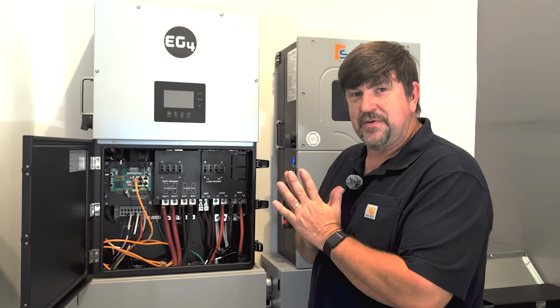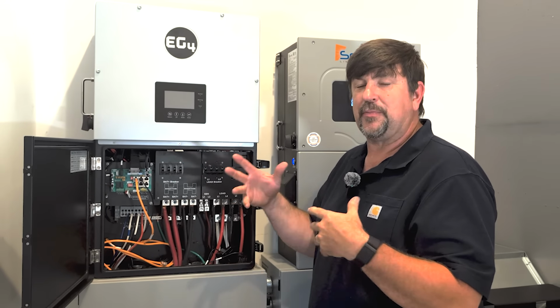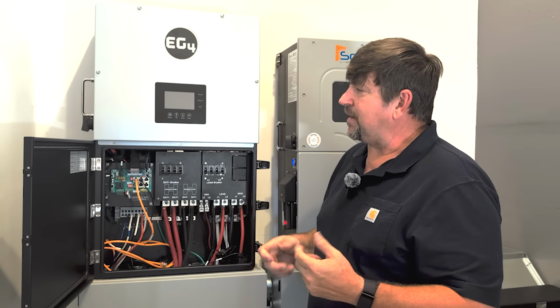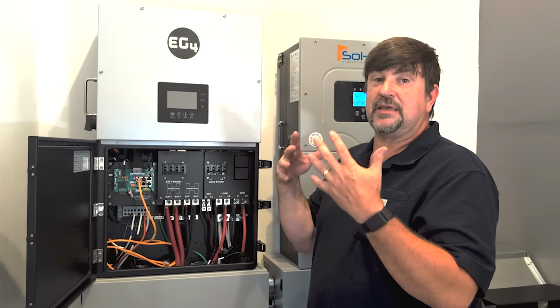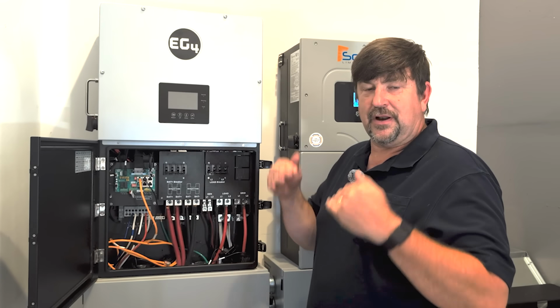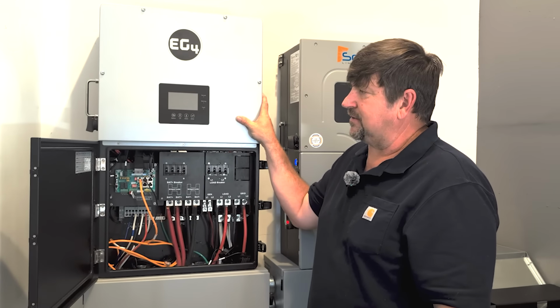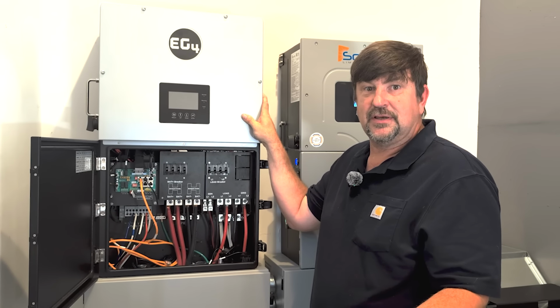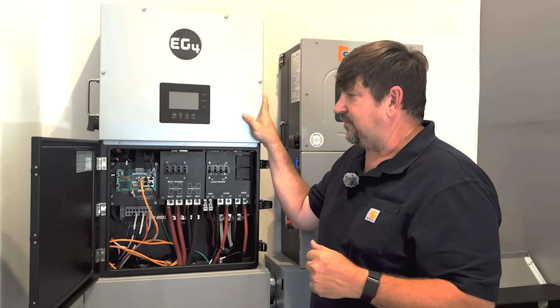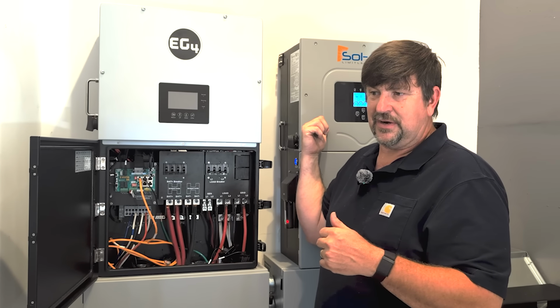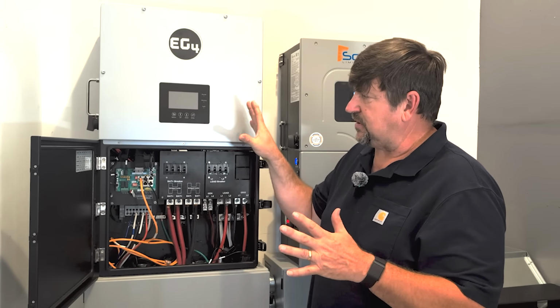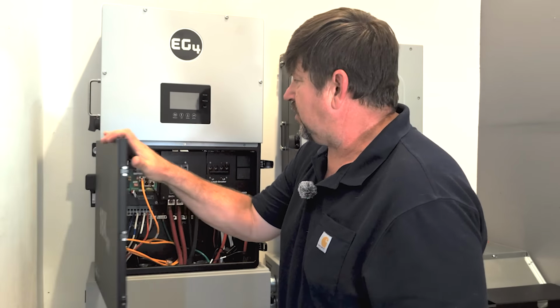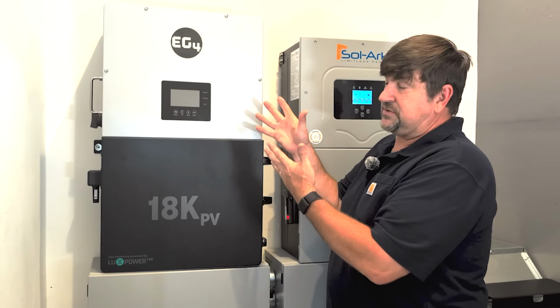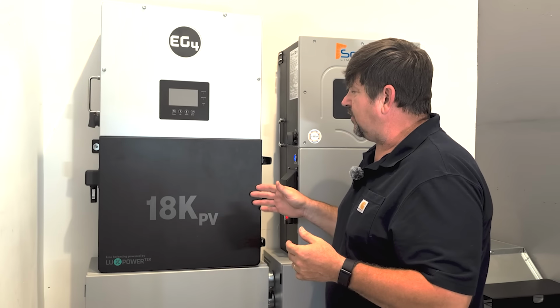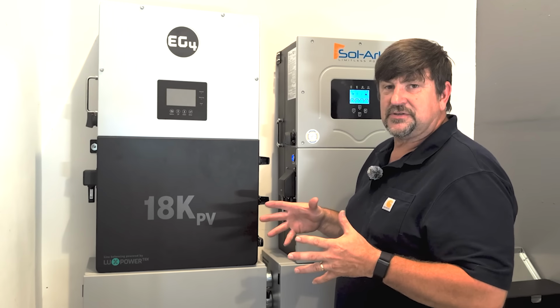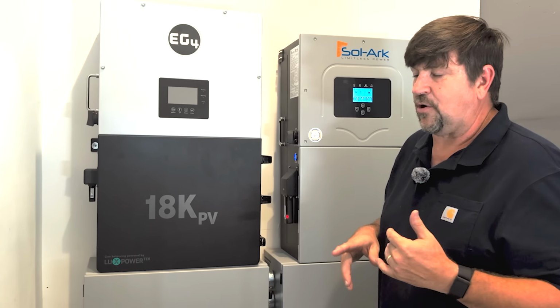Overall, yes it works, but we really worked it hard — I think it made it to about 45 minutes before it really started to overheat. Most people don't run like that, I understand, but my concern is if you get into loads like EV charging or Bitcoin mining, you'll have constant high loads working at the machine's capacity. It seemingly overheats, and at way too high a temperature. I've never seen the Sol-Ark go above 72 degrees Celsius working it super hard. This one doubled that — hot to touch, kind of scary. That bothered me. Is it just this inverter, the only one I've used? I don't know.